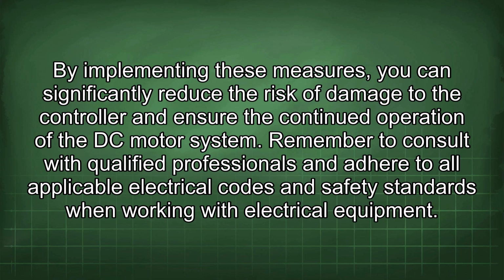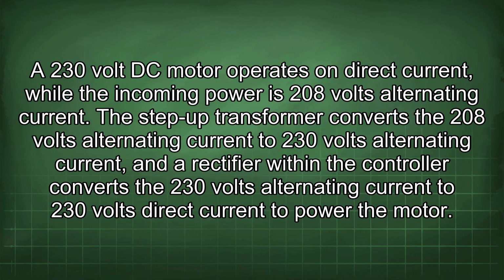Remember to consult with qualified professionals and adhere to all applicable electrical codes and safety standards when working with electrical equipment. A 230-volt DC motor operates on direct current, while the incoming power is 208 volts alternating current. The step-up transformer converts the 208 volts alternating current to 230 volts alternating current, and a rectifier within the controller converts the 230 volts alternating current to 230 volts direct current to power the motor.